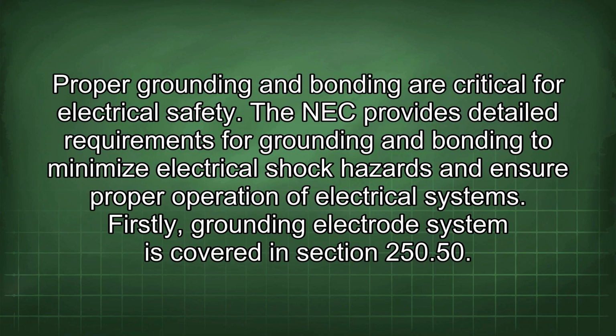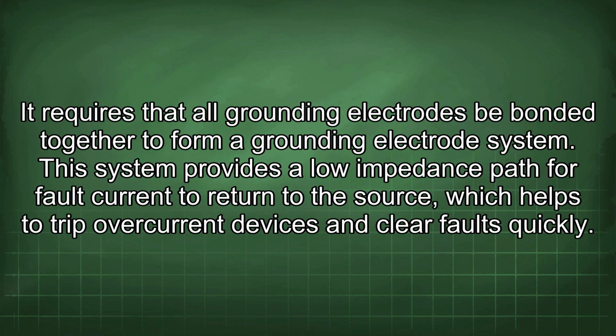Proper grounding and bonding are critical for electrical safety. The NEC provides detailed requirements for grounding and bonding to minimize electrical shock hazards and ensure proper operation of electrical systems. Firstly, grounding electrode system is covered in Section 250.50. It requires that all grounding electrodes be bonded together to form a grounding electrode system. This system provides a low impedance path for fault current to return to the source, which helps to trip overcurrent devices and clear faults quickly.